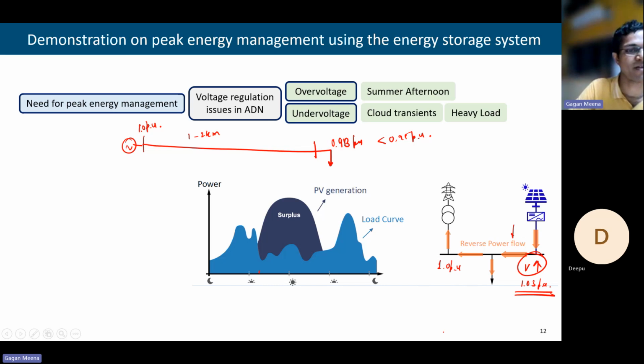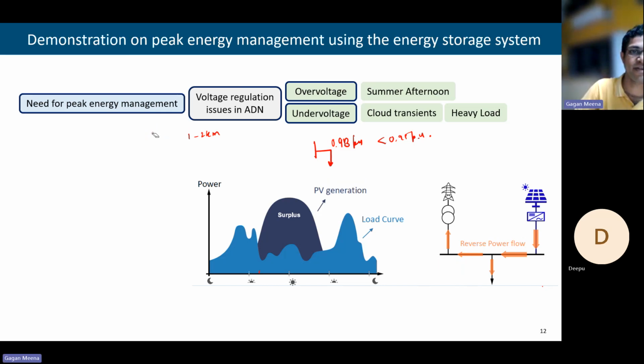So this is the reverse phenomenon. Earlier it used to be less than 1 per unit, now it is more than 1 per unit. And because of this, there is a reverse power flow. The same way, this happens when there is high PV output and the load is also less. But if PV output is less and load is more, then there will be a voltage drop, a low voltage condition.